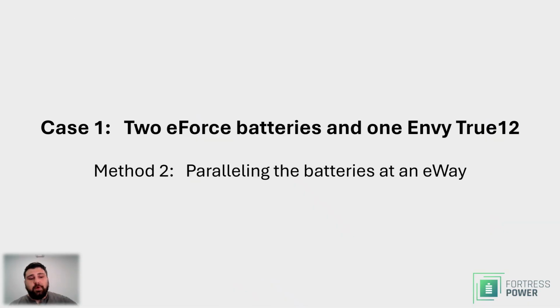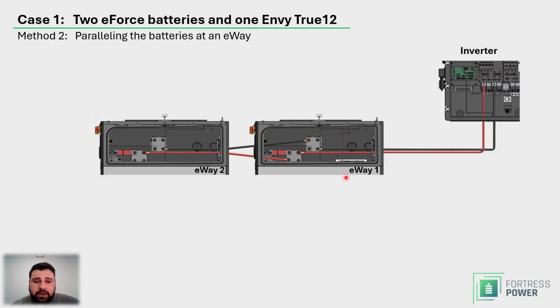Now let's switch to method 2, paralleling the batteries at an eWay. Previously we paralleled the batteries at the inverter. Now we're going to do the same thing, but not at the inverter, but at the eWay itself. We're going to use eWay 1 in this case. So 1 positive and 1 negative connects to eWay 1. These bus bars automatically are connected to the inverters, or inverter. In this case, we only have 1 inverter. And this eWay 1 is connecting the eForces, the imaginary ones that are underneath it, to the inverter.